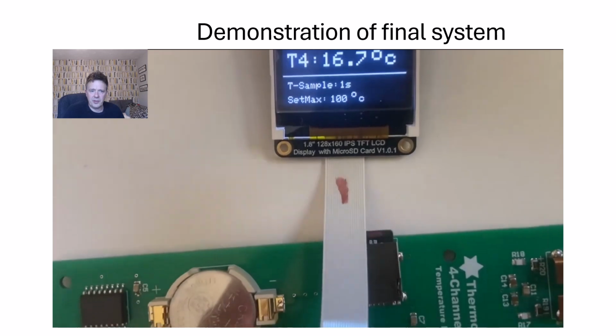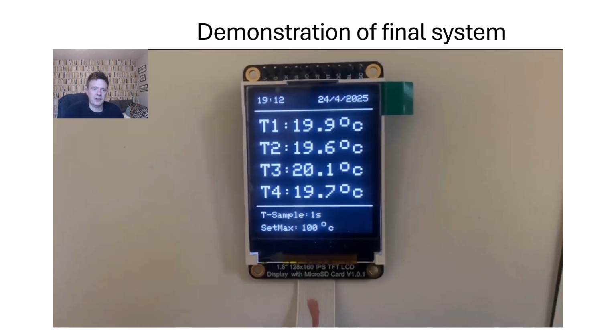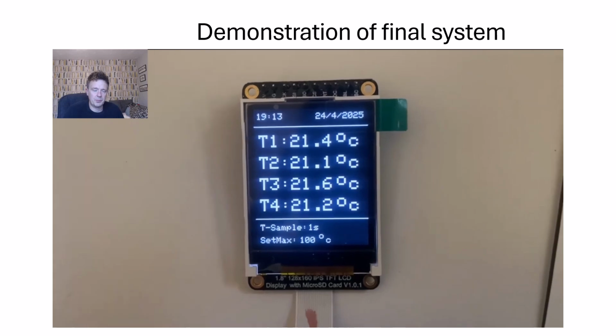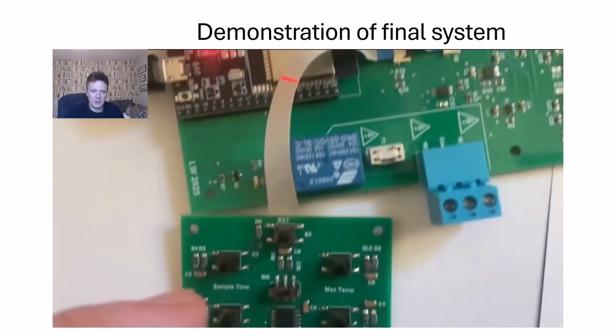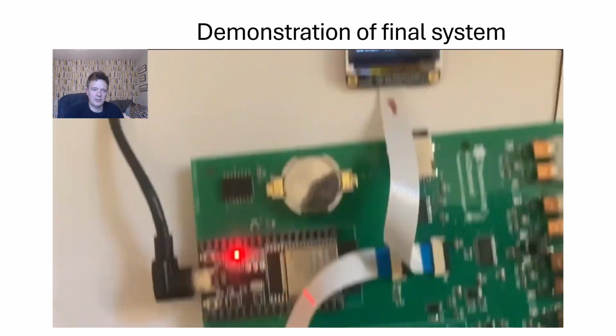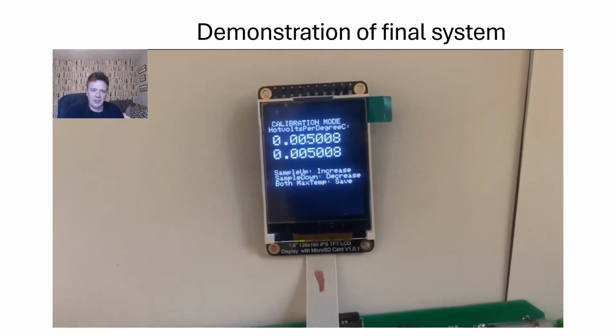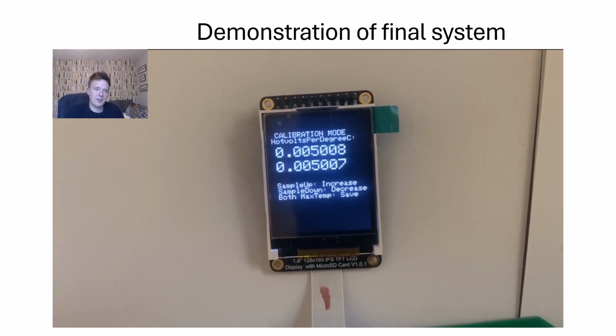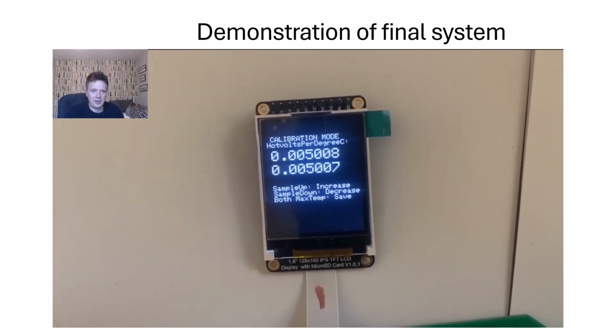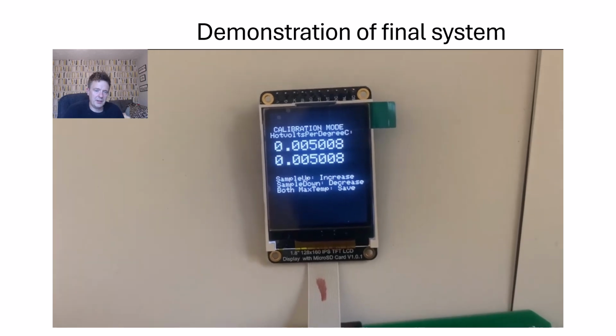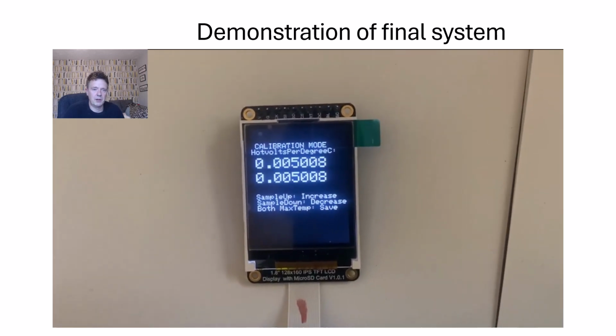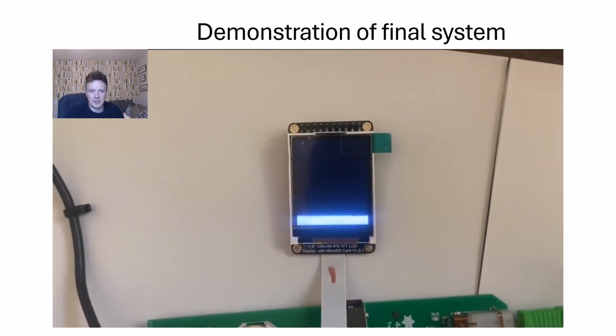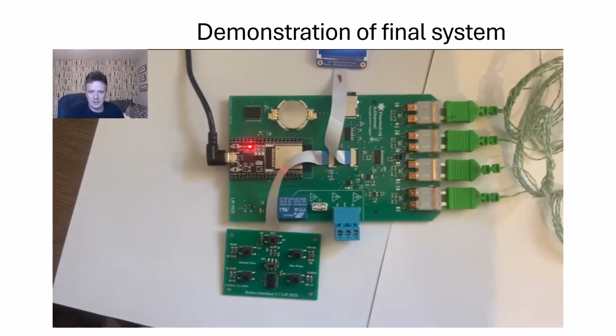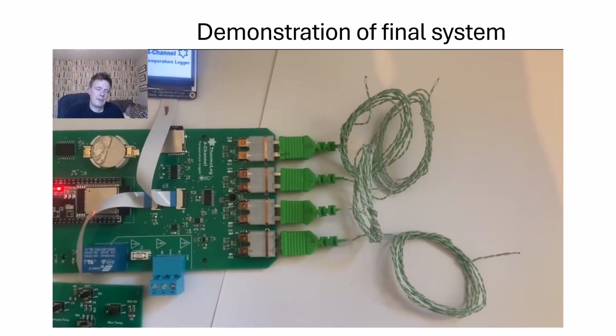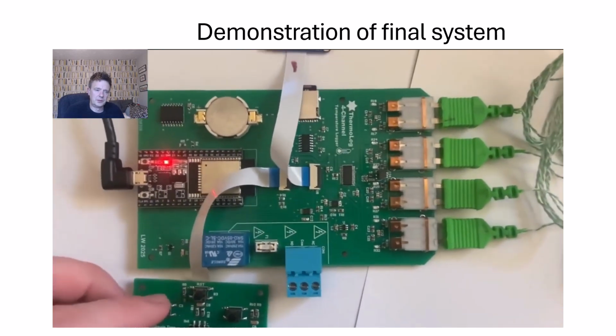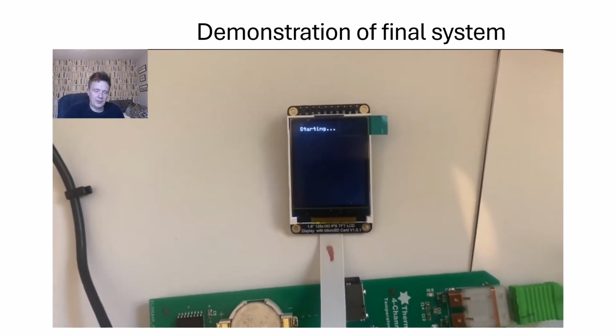So for the system I introduced an engineering mode, a calibration mode that you can enter by pressing two of the buttons on the user interface, the max temp buttons here. That shows the output scale factor of the operational amplifier, and you can change it from here, which gives you the ability to calibrate the system to any other system or other temperature standard. That has been calibrated to the values I use throughout this project. There are the 4 channels again, so we select all 4 of them.